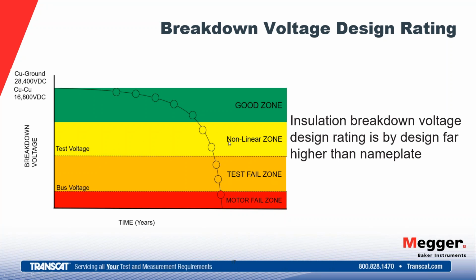This yellow zone becomes what we're calling a nonlinear zone. So if you have that increase in current from one step to the next that more than doubles, then that puts the motor here on the life curve. Again, depending on which voltage that occurs at, we're in what we call the nonlinear zone, which is above that test fail zone. So we're not failing tests, but we have an indication, the handwriting's on the wall, if you will, for this motor. We know we have a compromised insulation system, and we need to instigate a switch out of that motor. So again, to reiterate, it's not that the current doubles, it's the increase from one step to the next.